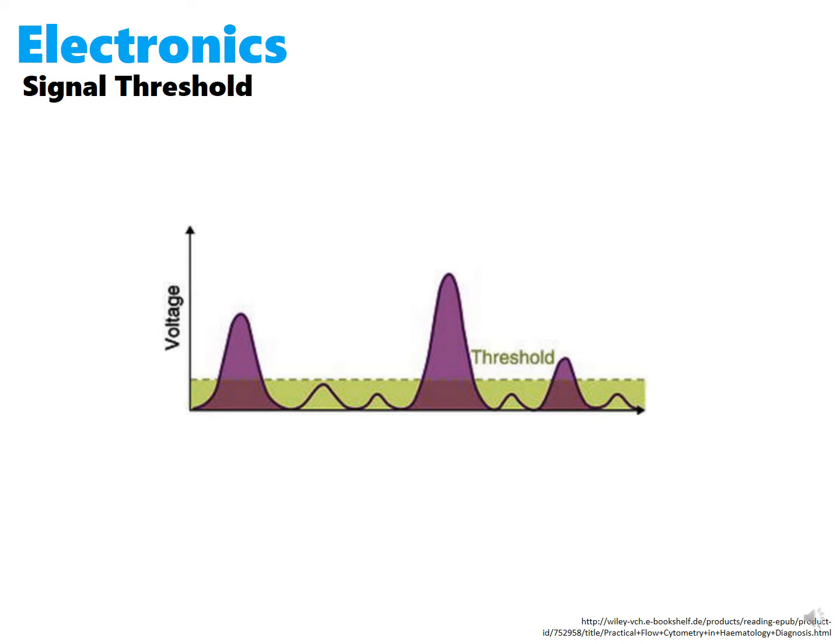These voltage pulses occur not only for cells but also for any particulate debris that pass through the laser. In order to avoid interference from any debris, we need to have a signal threshold. Signals below the threshold are not processed. However, one must be careful because if the signal threshold is too low, we'll have extra noise added into our signal. But if the signal threshold is too high, we might miss the cells of interest.